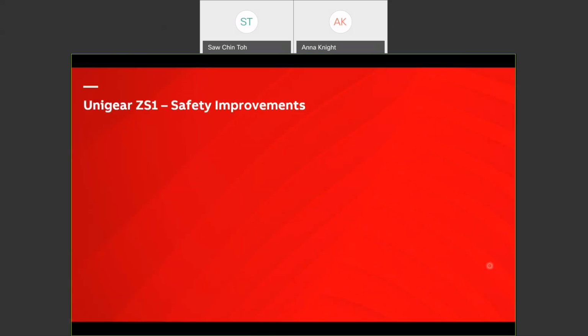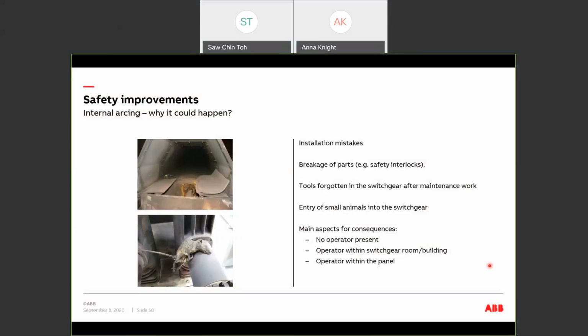When it comes to medium voltage switchgear, safety is a very important thing. Many a time we want to try to avoid the internal arc event in medium voltage switchgear. But sometimes it's not avoidable, because the main reason causing the fault is unfortunately man-made error. For example, installation mistakes, or operation mistakes by bypassing or damaging the safety interlocks, or tools being forgotten in a switchgear, and when we turn on the switchgear it will create an internal arc fault. The consequences of such an event are huge, and it will impact the operator as well as causing damage to the assets.